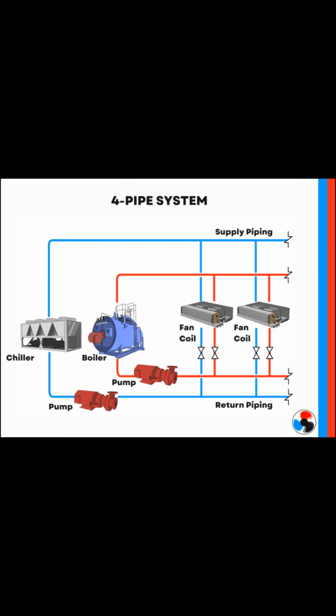Hydronic systems use water as a transmission media. Water is cheap, readily available, has high thermal conductivity, and high specific heat. It has a 100-year history in the heating industry, and that has made parts cheap, readily available, and fairly interchangeable. Heated or cooled water can be transmitted long distances in tight spaces, enabling heating or cooling equipment to be conveniently located on roofs, in boiler rooms, or in district heating plants.